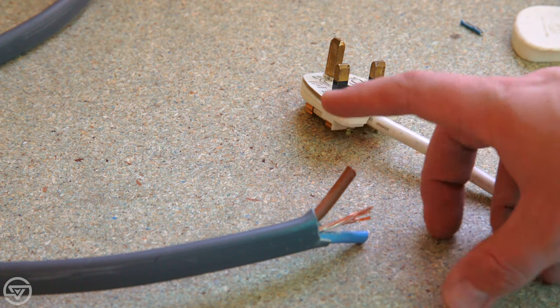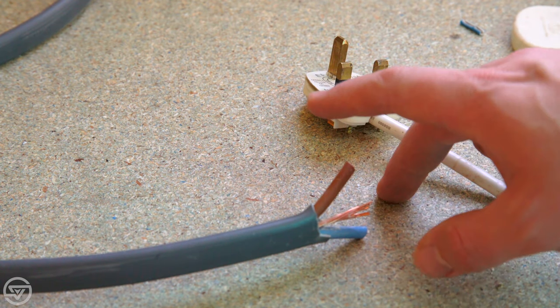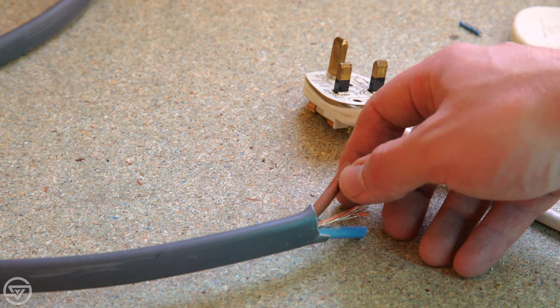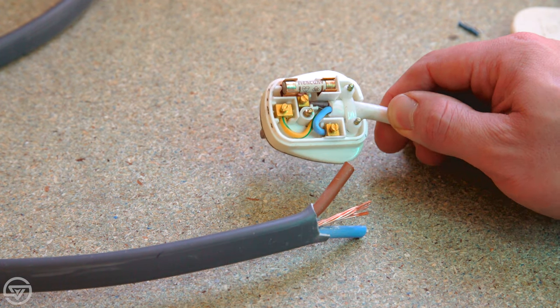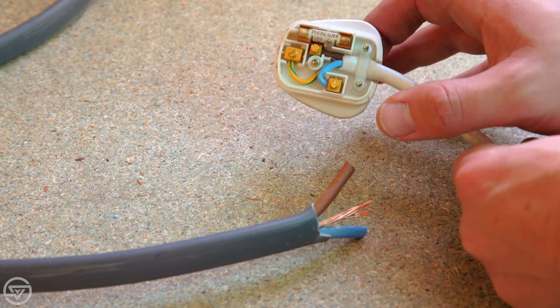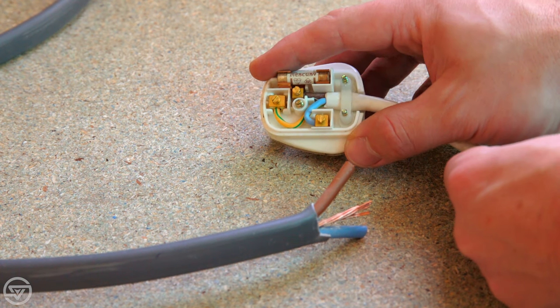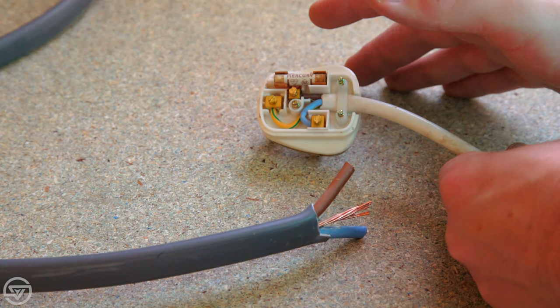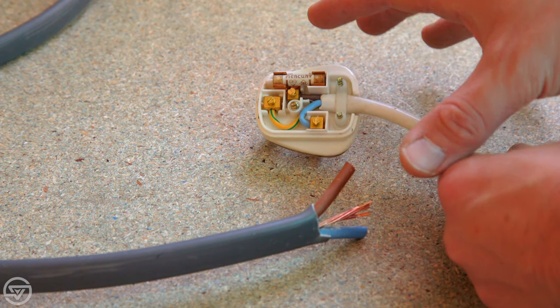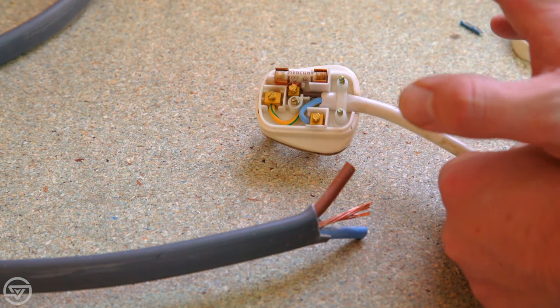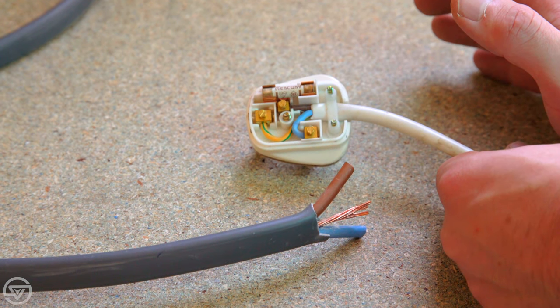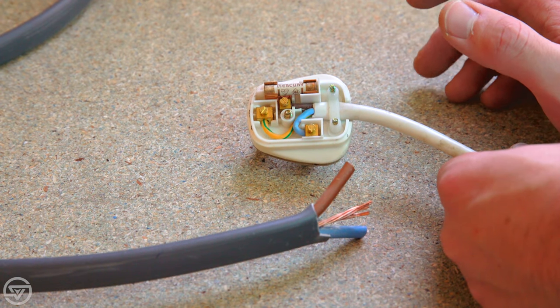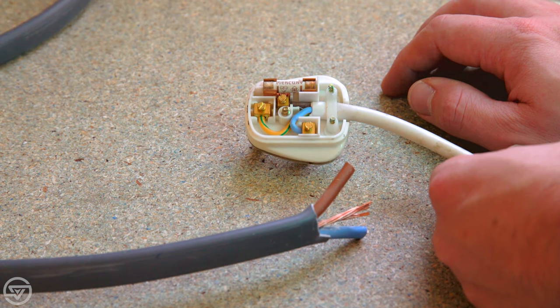This is the supply cable. It's a 10 mil cable, easily capable of handling 40 amps. Eventually when I connect that into my home fuse board at a 32 amp circuit, this will be more than enough. In the meantime, I'm going to wire it in through a UK power plug. UK power plugs include a 13 amp fuse, so if I wire the entire container through the fuse board via one of these power plugs, the container is considered an appliance. That means we don't have to notify the council of works and get all sorts of sign-offs and testing done. The container will be limited to running 13 amps at 240 volts, but that's more than enough for the time being.